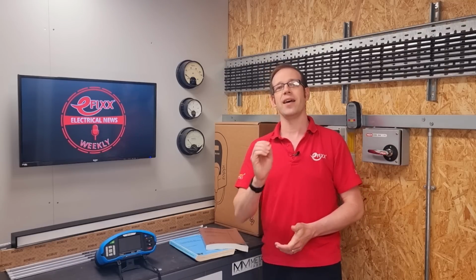The final hazard is arc faults and arc flashes. Arc faults between 2 or more conductors can result in discharge, causing heat that can lead to the deterioration or even to the burning of wiring insulation. PV systems are particularly vulnerable to arc faults caused by disruption in conductor continuity or by unexpected current between 2 conductors, often the result of ground fault.